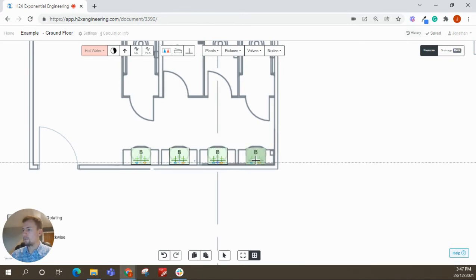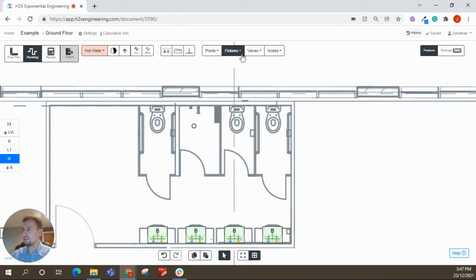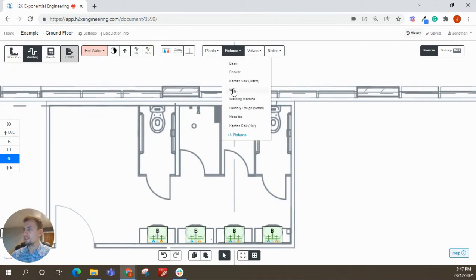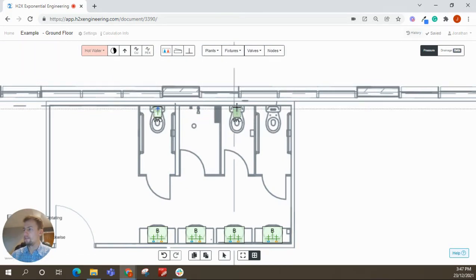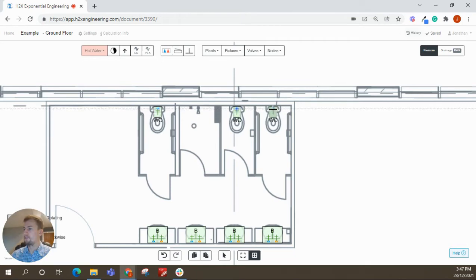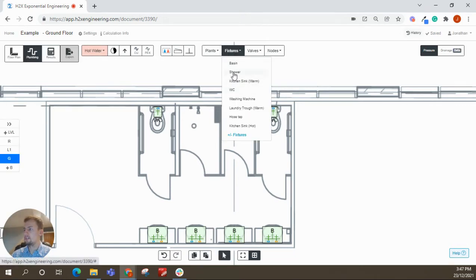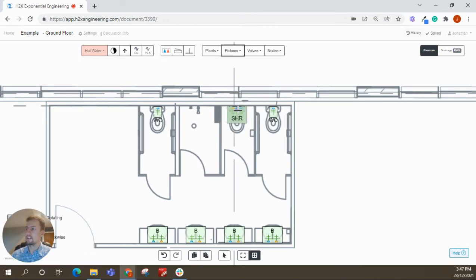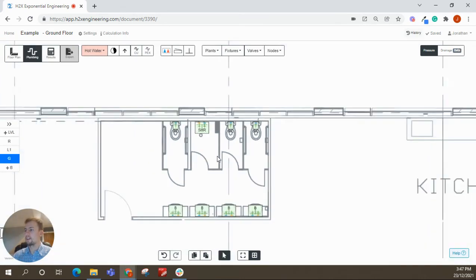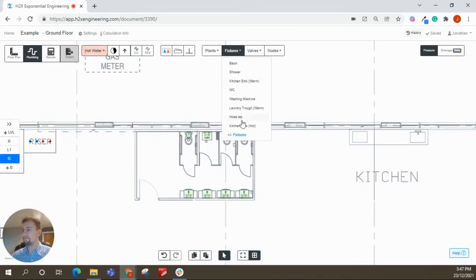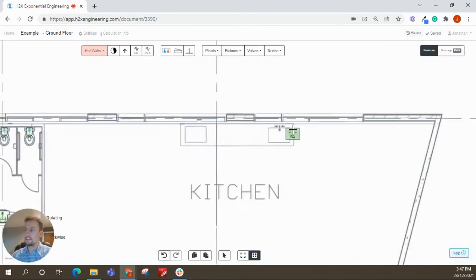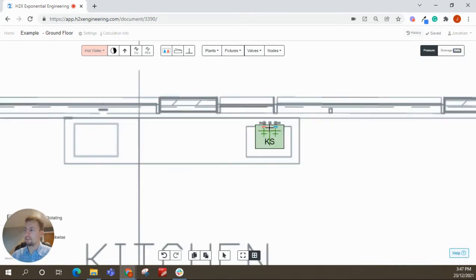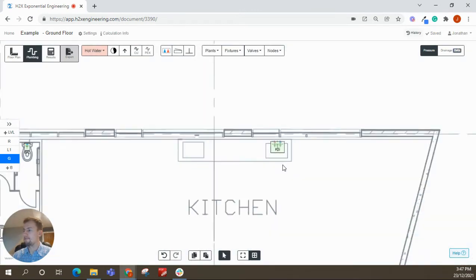So the way this works is these fixtures have loading units assigned to them. So that as the pipes connect to them, the loading units can be recognized through the pipes. And then that is then converted to flow rates using the peak flow rate calculation method. And then that's how, once you've got the flow rate and the pipe size, you want to have velocities and pressure drops and things like that.